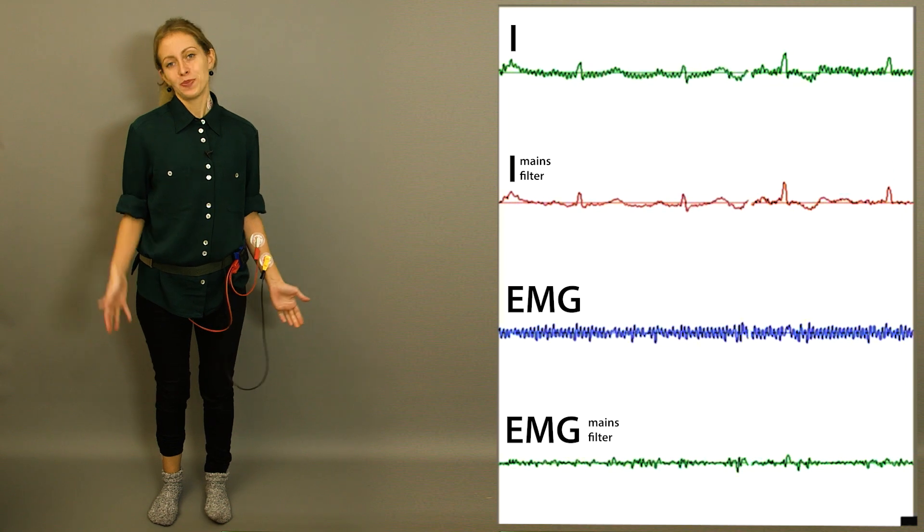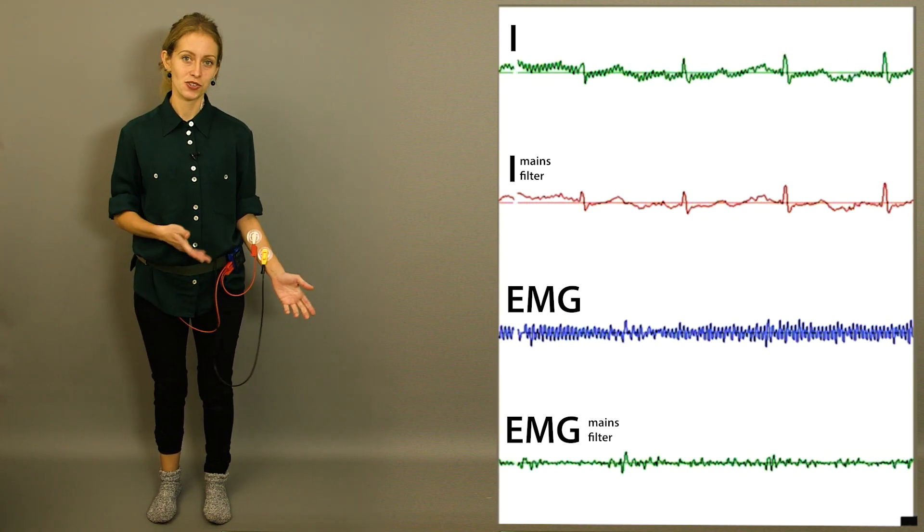Well, three electrodes will give you a much better power line rejection than the two electrode version.